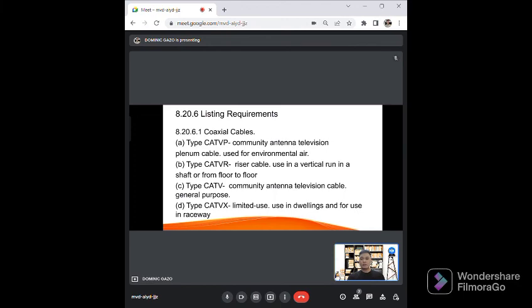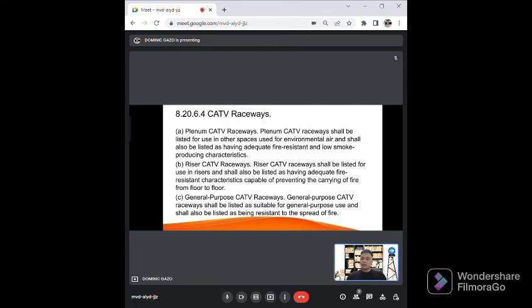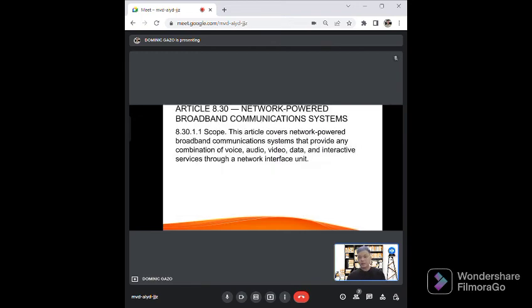The type CATVP for the antenna communication plenum cable, and it is used for environmental air. For CATVR, the riser cable for vertical run. For type CATV, community antenna television cable for general purpose. For CATVX, it is used for dwellings and used for raceway. And for Article 820.6.4, CATV raceways, we have plenum, riser, and general purpose raceways. And then for Article 830, network powered broadband communication systems.